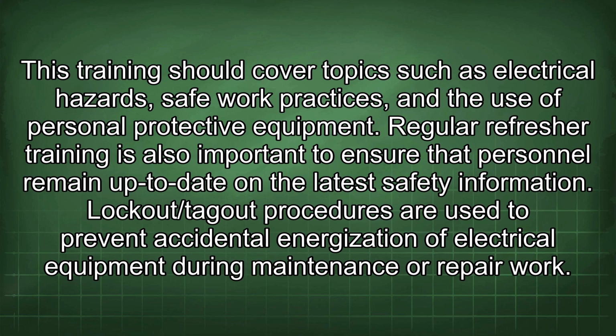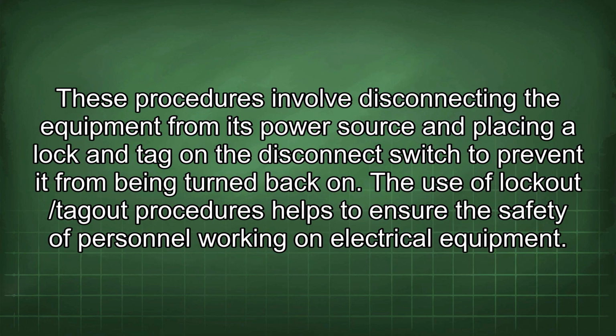Lockout/tagout procedures are used to prevent accidental energization of electrical equipment during maintenance or repair work. These procedures involve disconnecting the equipment from its power source and placing a lock and tag on the disconnect switch to prevent it from being turned back on. The use of lockout/tagout procedures helps to ensure the safety of personnel working on electrical equipment.